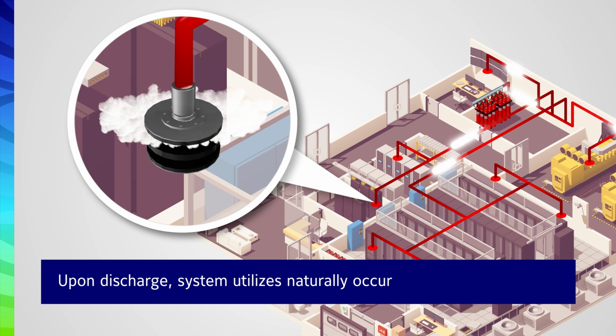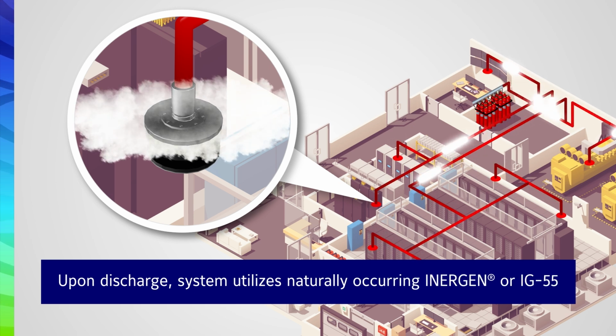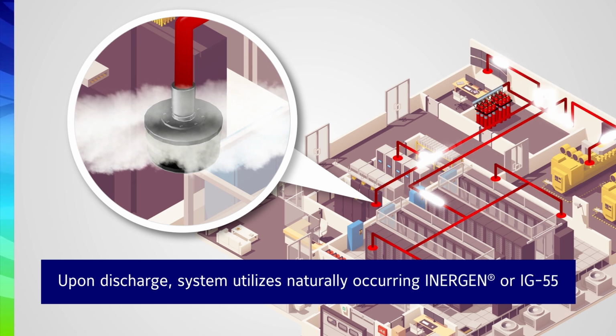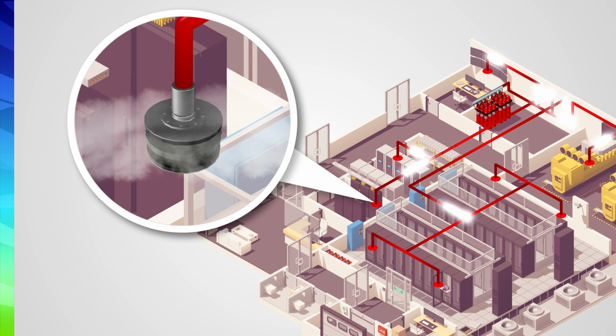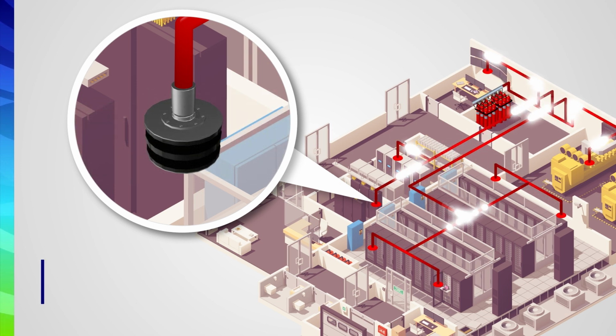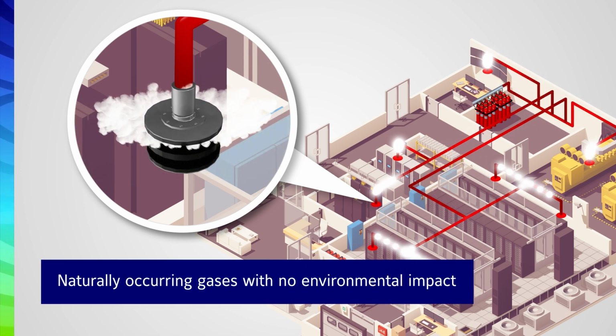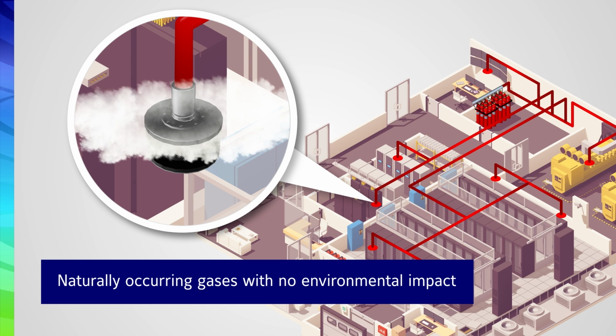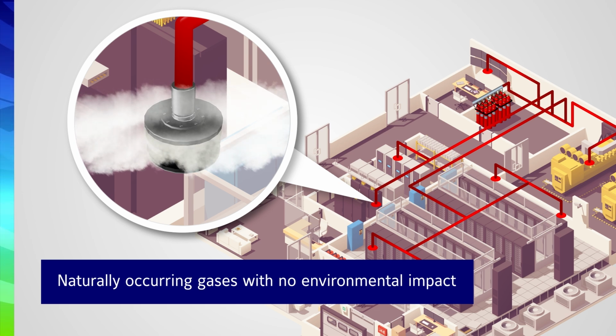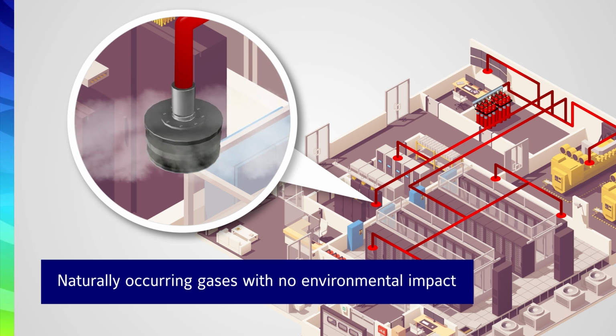Upon actuation, the HYGOOD IGS 300 discharges environmentally friendly Inergen, or IG-55, from a centralized bank of containers and is safe to protect occupied spaces. The naturally occurring gases flood the protected space, displacing oxygen. The agent has no global warming potential or ozone depleting potential.